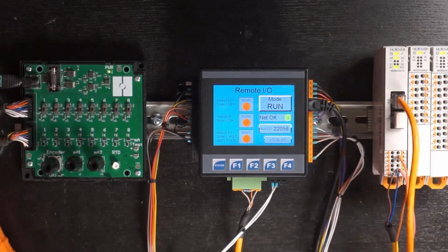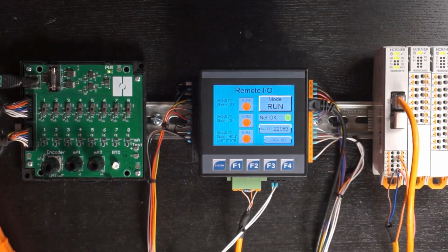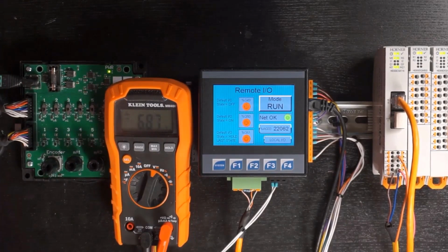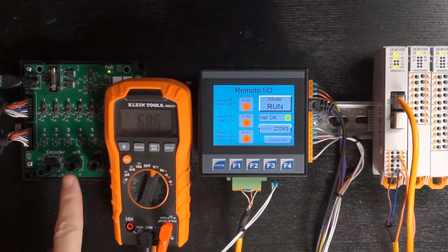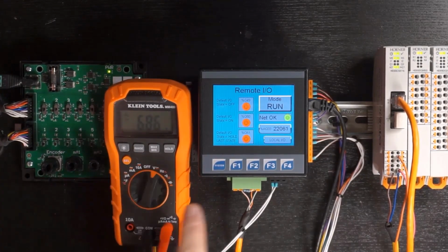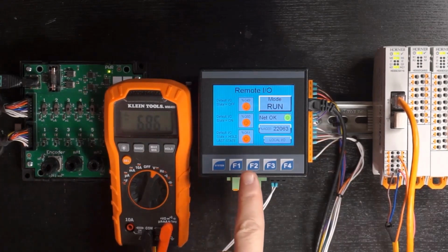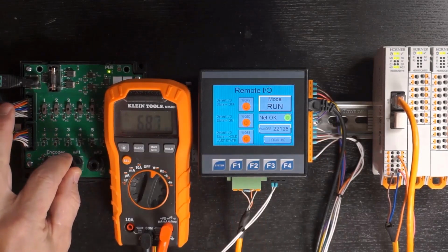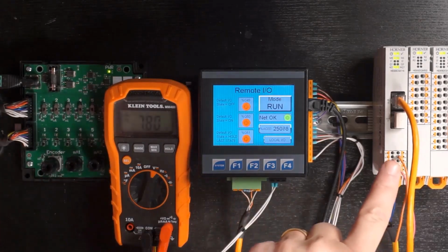Next, we will look at what is happening with the analog output on our remote I/O base. To do this, we will be using a multimeter. Once again, the two pots on our I/O simulator are wired as analog inputs to the OCS. So our OCS is passing this value from the first pot directly over to the analog output register that is controlling this analog output.